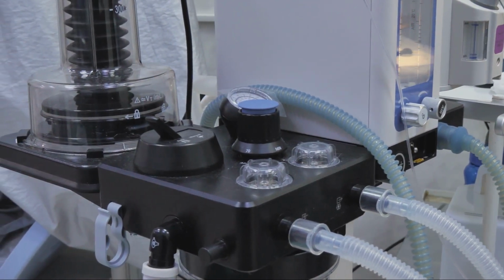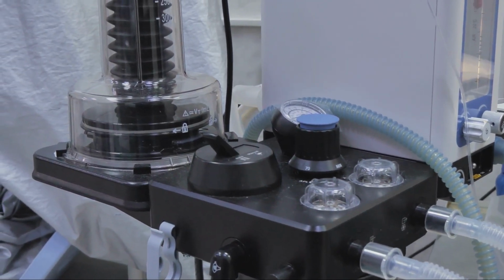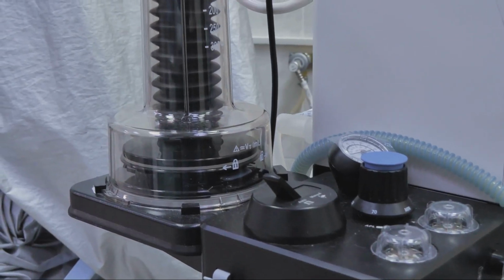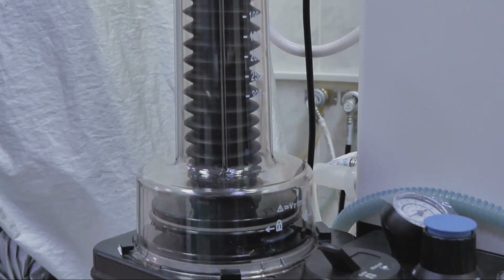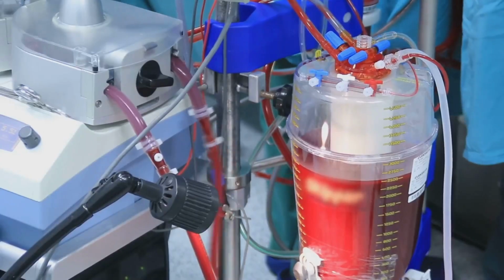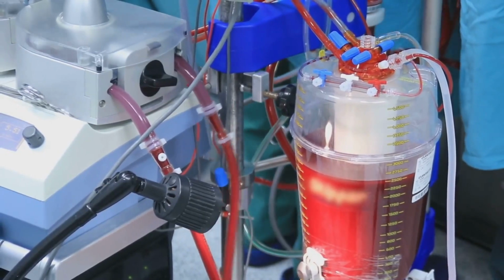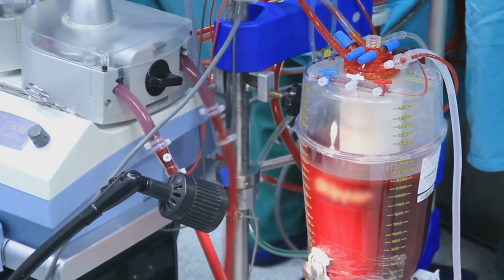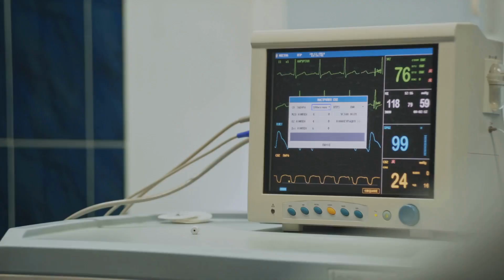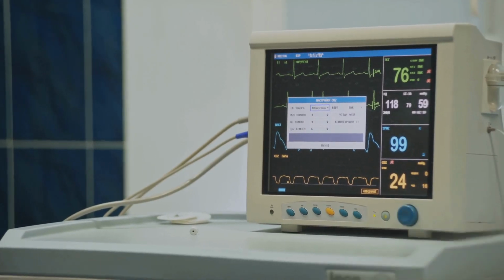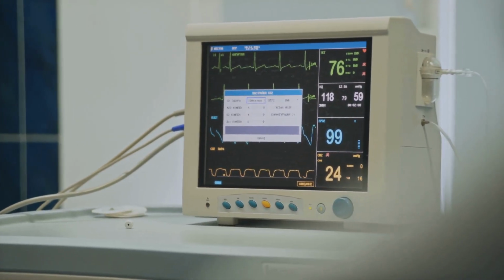This system begins at the flow control valves and ends at the common gas outlet. Here, the pressure is reduced even further, to just above atmospheric pressure. This district is like the city's residents, receiving the pressure and utilizing it in the most effective and efficient way possible. Each of these systems, these districts, is integral to the overall operation of the anesthesia machine.